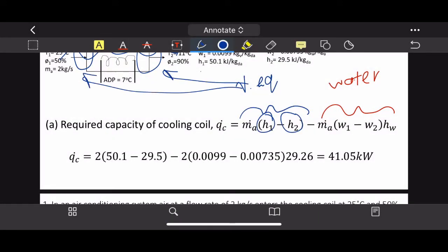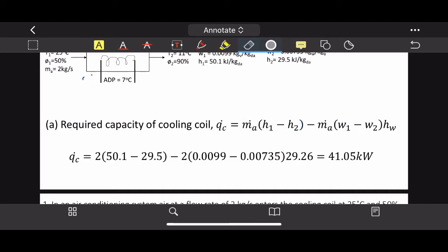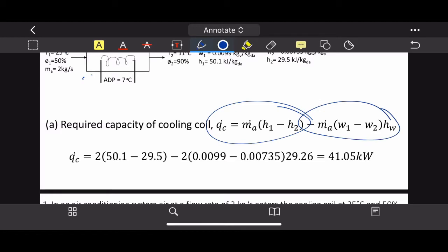The second part of the equation accounts for water energy: water that moves in and out of the system exchanges energy in the form of heat, even without exchanging mass. That's why we combine them in one equation. The full term with enthalpy is larger than the water term, and the answer is a positive value, meaning energy is absorbed by the cooling coil — hence we call this the cooling capacity of the coil.